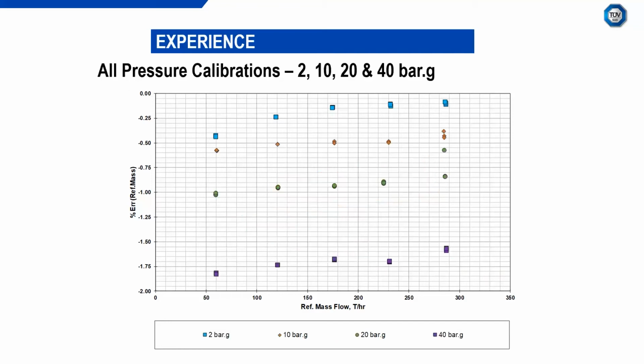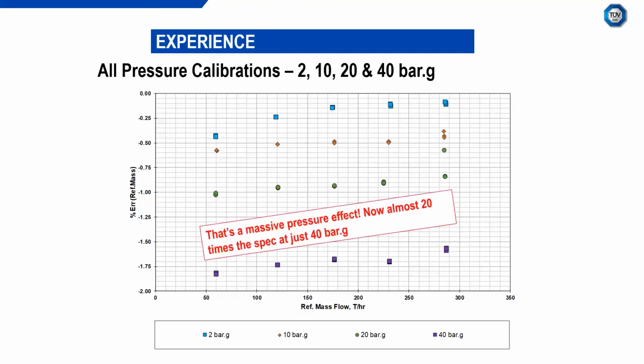So we've got 10, 20 and 40 bar gauge, and I've still got the 2 bar data. We can now see the effects of operating at 10, 20 and 40 bar gauge with this 6-inch flow meter. You can see that there's a definite pressure effect here. As pressure increases, now at 40 bar, we're under reading by 1.75%. That's fairly significant. It's a massive pressure effect. It's almost 20 times the specification when you're operating at just 40 bar gauge.